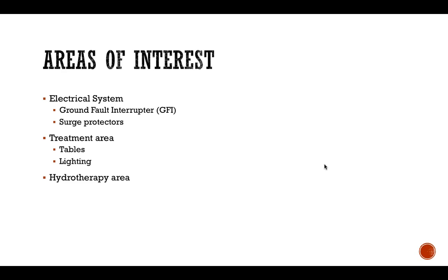If you're going to have shortwave diathermy in your facility, they recommend all wood tables versus metal tables. Shortwave diathermy uses electrical magnetic currents, and so sometimes having too much metal in the area can kind of mess with that system. Ideally, you want 30 inches apart, but that's the minimum. Ideally, you want even more space, because you've all been downstairs when it's tight and you have multiple people and you have two clinicians trying to work on either side of a table, and you're trying to do range of motion exercises or, you know, stretch someone out, and it's crowded.